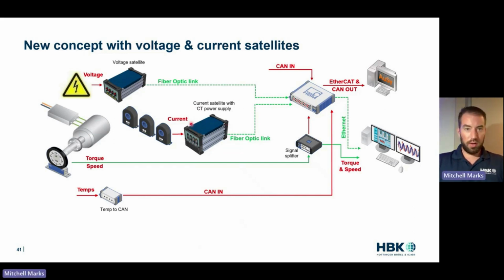We're coming out with what we call our satellite modules - a voltage satellite, which handles 4 voltages, and a current satellite, which handles 4 currents. The goal is to shorten those cables to be as short as possible, like 10 centimeters, so we have less distance for coupling that high dV/dt, and less copper cable to make it confusing. 4 voltages come into the voltage box with 1 cable back to the unit, and 4 currents come into the current box with 1 cable back to the unit - really shortening those measurement cables and bringing everything back to one common cable.